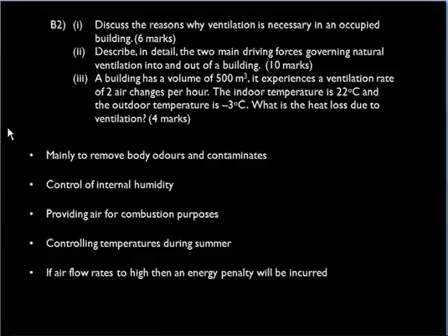We need to provide air for some combustion processes, and now most gas appliances tend to have a balanced flue, so they bring the air in from outside. But in some instances, particularly say gas cookers, they will need to have a supply of air for combustion purposes.